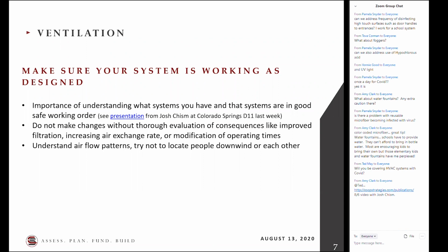I know that there's been really good success when you shine an ultraviolet light onto a heating and air conditioning coil, especially if you have good pre-filters, in keeping fouling and microbial growth off of the cooling coils. I don't know much about in-duct systems, but intuitively, the air's moving too fast through the air duct to get enough irradiance to kill anything. And you still need good filtration on top of that too. So I would stay away from that, I don't think it's worth it.